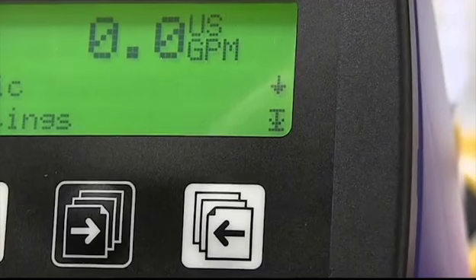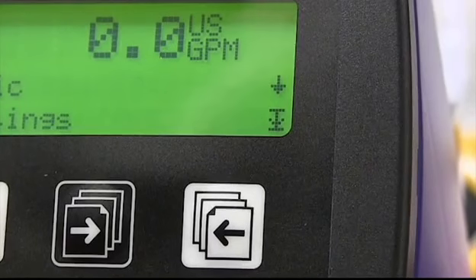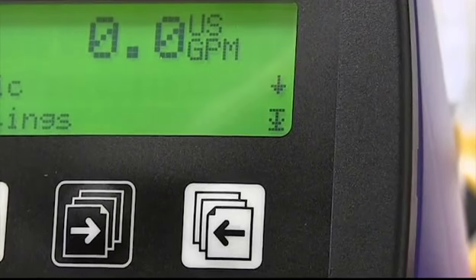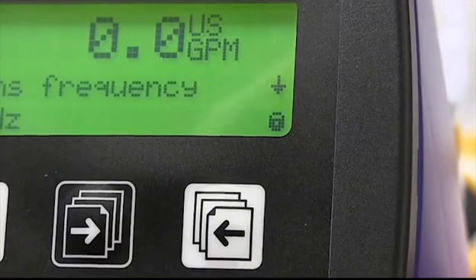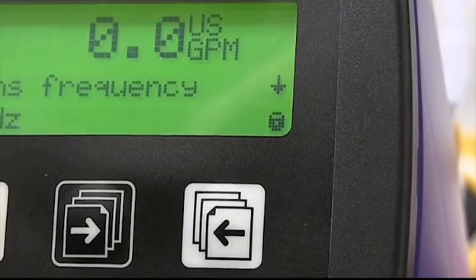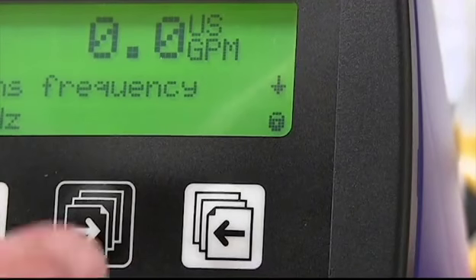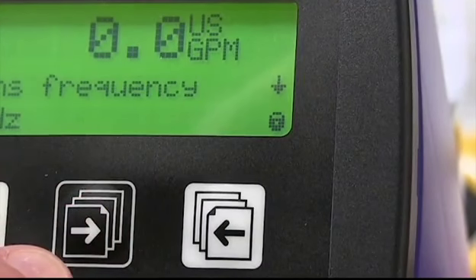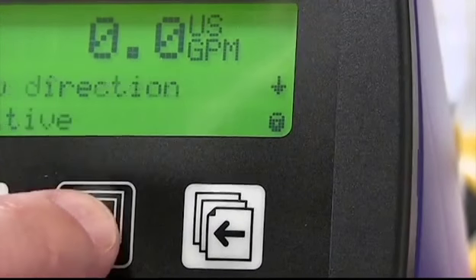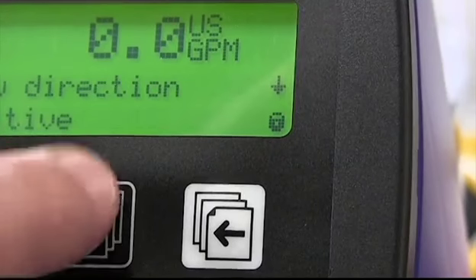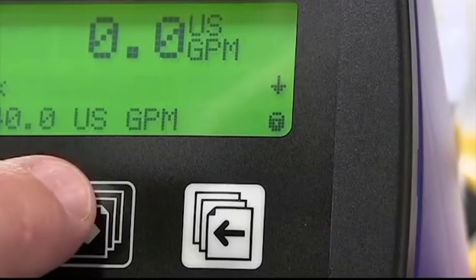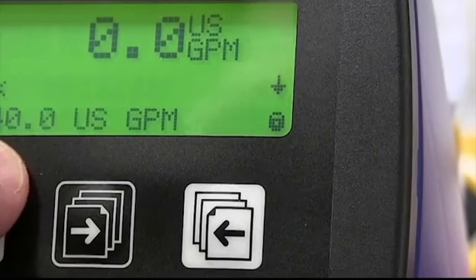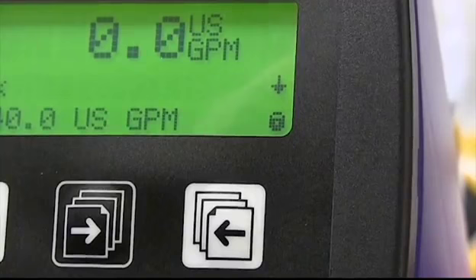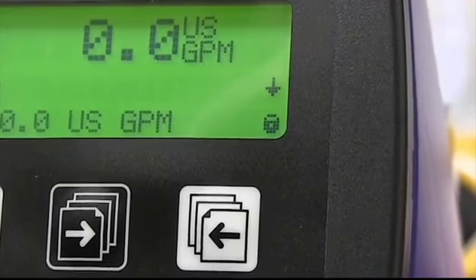Now as you can see, there's an arrow on the right hand side indicating there are more parameters below this setting. So press the lock unlock once and it comes up with your mains. If you keep on going through, you hit the black page with the white arrow, continue through. Its flow direction is positive. Qmax is set to 40. Now in this case, Qmax stands for your upper range value for these particular transmitters.